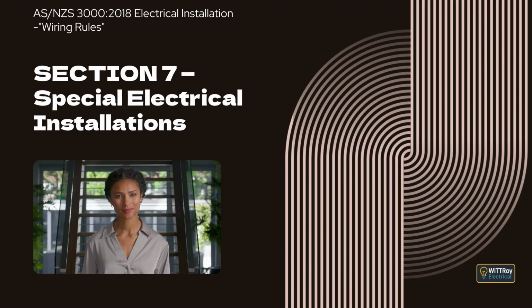The clause also explains that any switch controlling safety services in such a fire-separated portion must be separated from switches used to control the general electrical installation and other safety services. Clause 7.2.5 Fire pumps and fire pump control equipment. This clause introduces the requirements for electrical installations supplying fire pumps and their control equipment. The intent is to ensure that these systems remain reliable during emergency conditions.